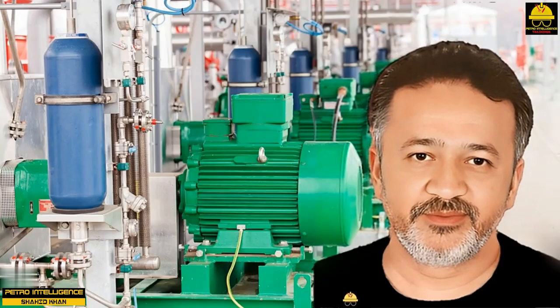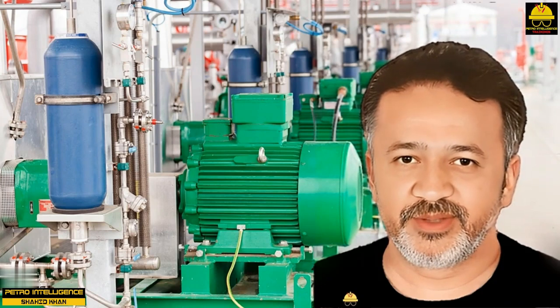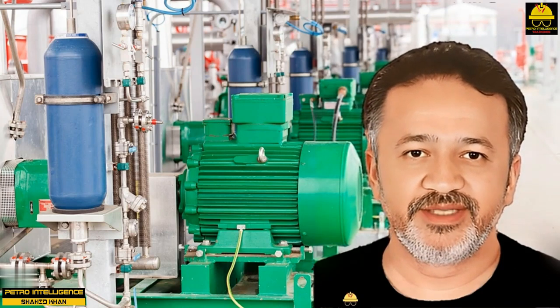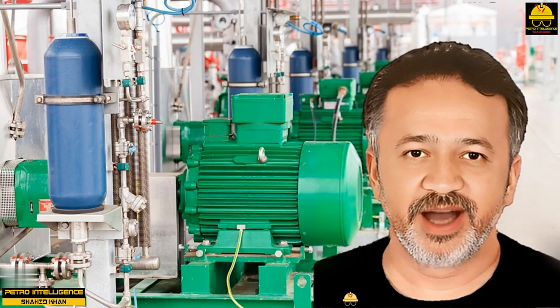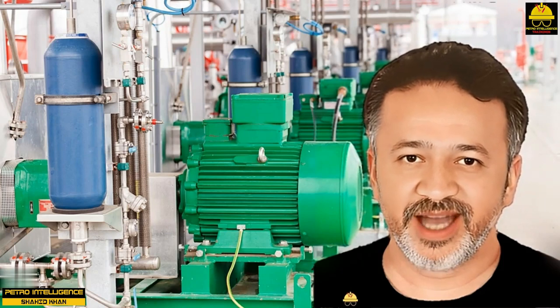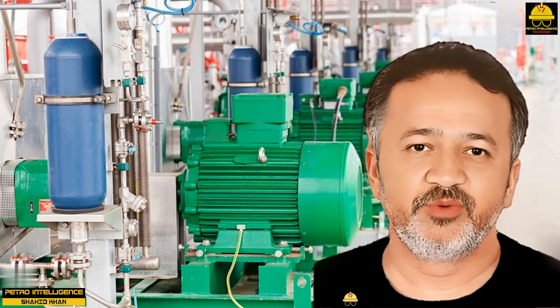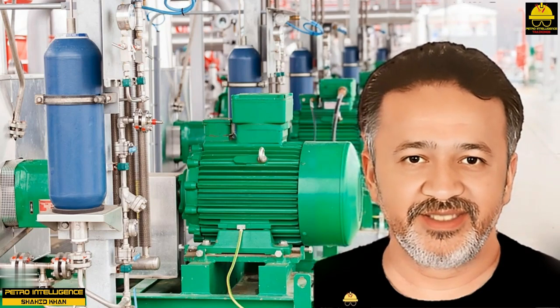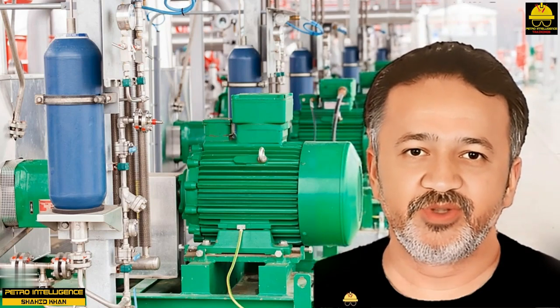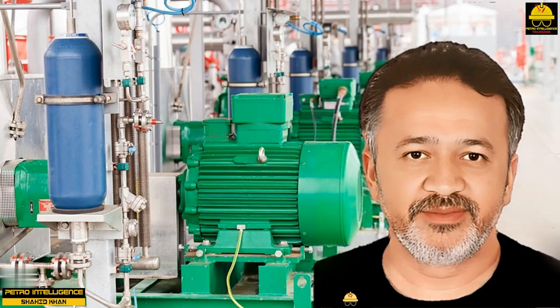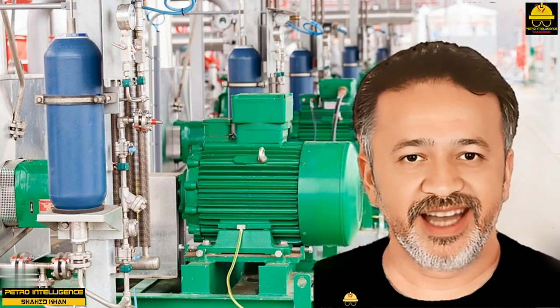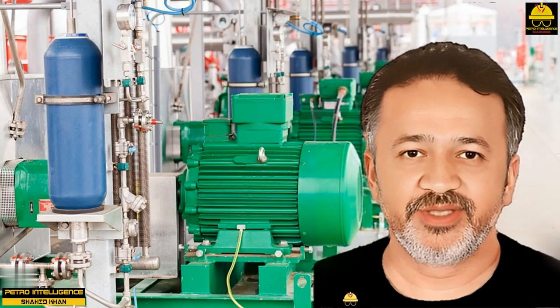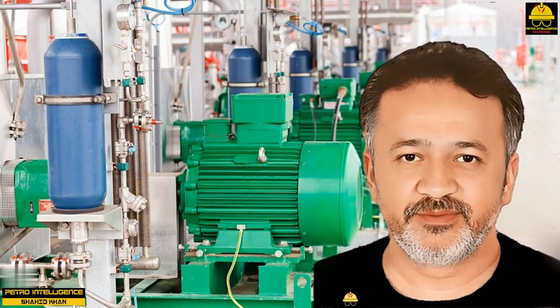Seals and bearings. The PC pump uses mechanical or soft packing to prevent leakage. The bearing housing is located on the drive shaft end of the pump. Large roller bearings designed to handle excessive loads protect the drive shaft as it transmits torque through the bearing housing. Because of this unique design, PC pumps can be adapted to use belt or direct drives.